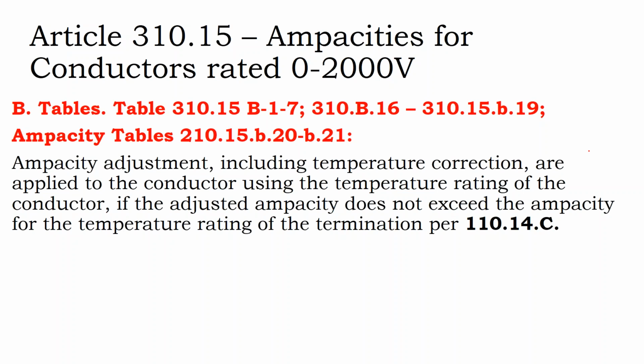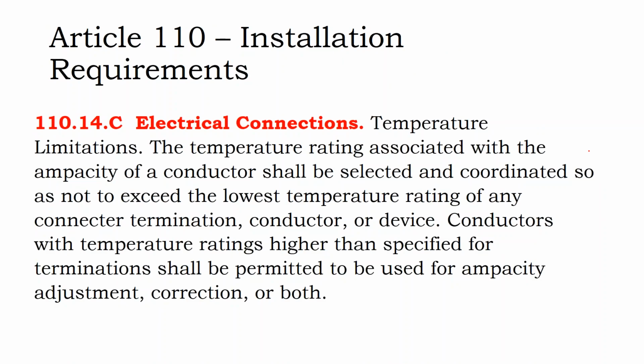So you need to do an ampacity and temperature calculation at the terminal to make sure that your 75C terminal is not exceeding its temperature rating. And then you can do your calculations for your conductors, 90C conductors at 90C. But you also have to go in and do a separate calculation at your terminal to make sure you're not elevating the temperature of your terminal, which is usually a 75C connection, just because of the way things are listed in the US per UL. They've never really stressed so much of a 90C connection. There's not too many uses for a 90C connection, except now there are, since we're using our rooftop more.